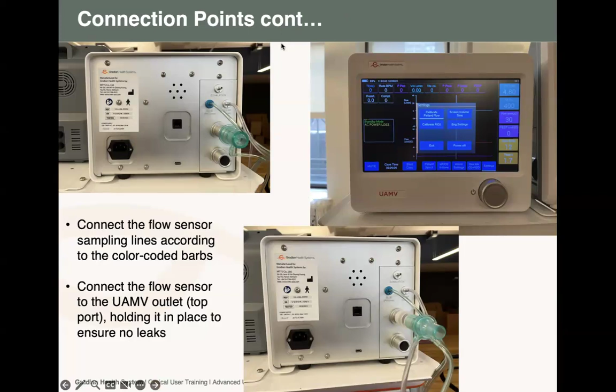On the front side, you are doing kind of the same steps, because you go on the patient calibration, patient flow. And as you have said before, the new UAMV has an oxygen sensor inside. You can also calibrate in oxygen. I'll skip this for now because we'll discuss it at the end of the discussion. So, going back to the connection and the flow calibration. Next, Maria.